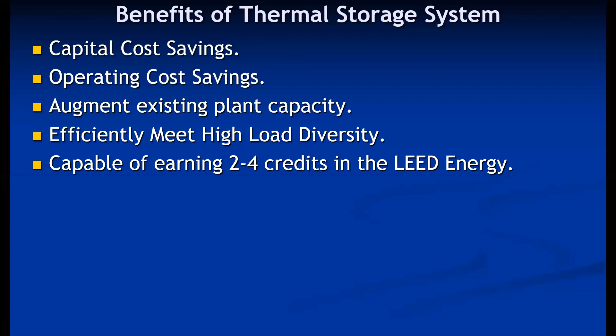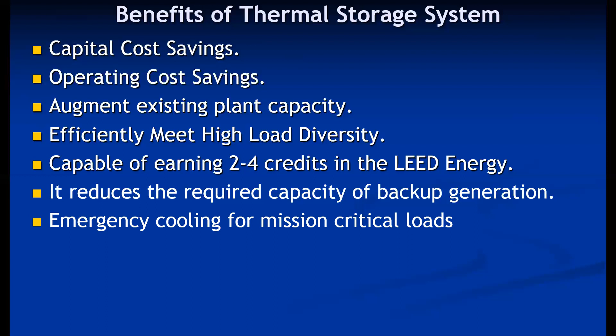It reduces the required capacity of backup generation. So the DG backup required is also reduced, because at the time of breakdown, the storage tank can be used. The energy which is stored can be used during breakdown or shutdown conditions. So less DG capacity backup is required, because a thermal storage backup is already available. So electricity backup requirement is less. Emergency cooling for mission critical loads: so it provides emergency cooling.